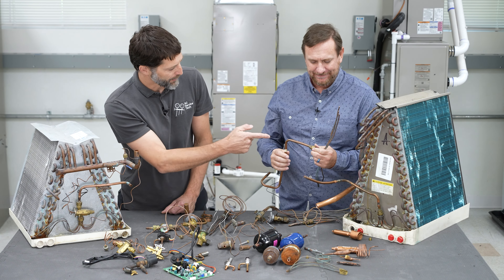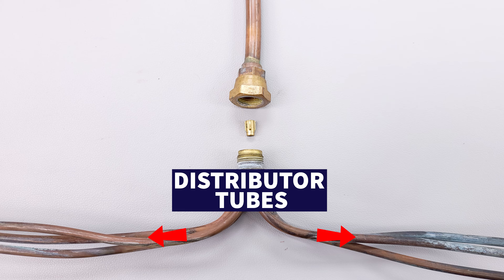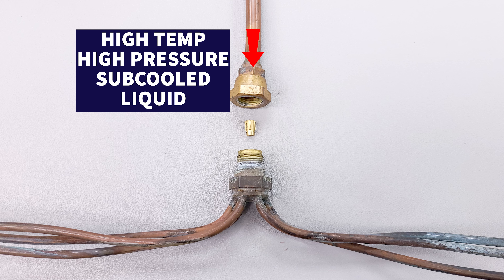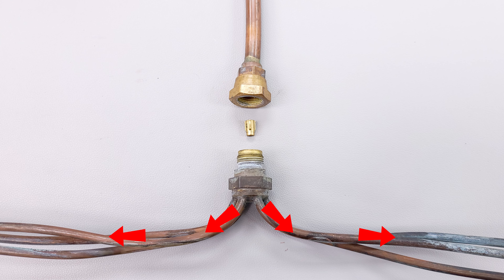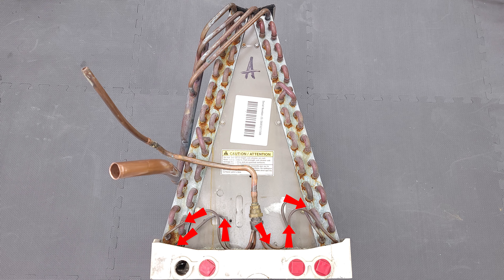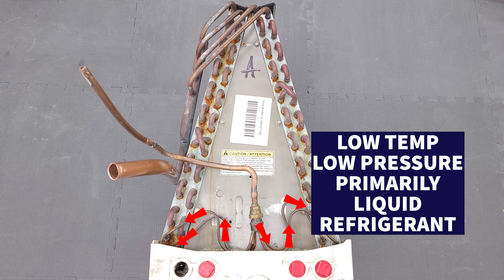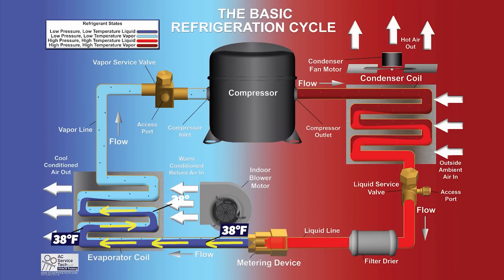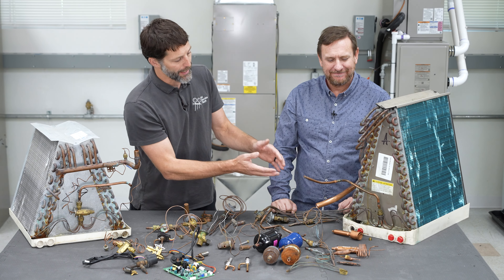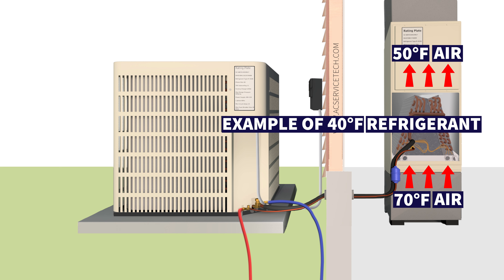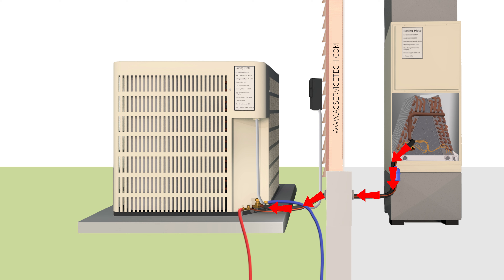On these fixed orifices — like what Ty's holding right here — these are distributor tubes. On a fixed orifice like this one, you have high-pressure, high-temperature subcooled liquid entering this restriction, which lowers the pressure, and then it goes through these distributor tubes to distribute refrigerant to multiple points inside the evaporator coil. The refrigerant is now a low-pressure, low-temperature, primarily liquid refrigerant — with a little flash gas because you're lowering the pressure — and it undergoes a phase change for most of the interior volume of the coil, absorbing heat and carrying it out to the outdoor condenser where it will be rejected.